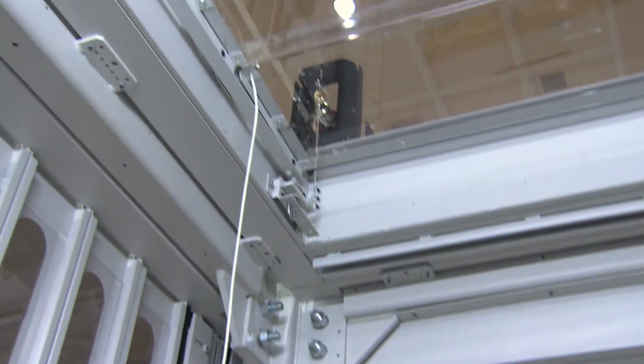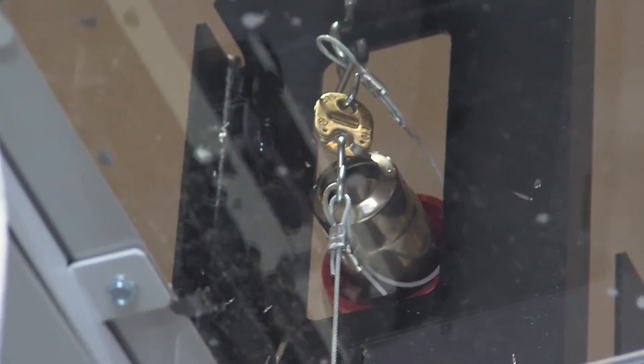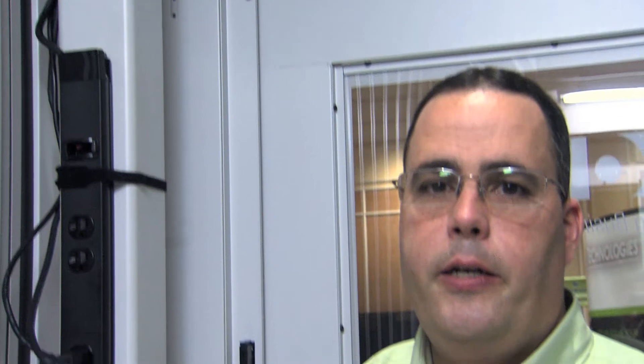The system works as follows: there's a fuse link up above that melts at 135 degrees Fahrenheit. When the fuse link separates, the linkage engages. Once the linkage is engaged, it has a mechanical advantage over the sealing panels, and they'll rotate 90 degrees, which will allow your fire retardant system to actuate and penetrate the aisle.